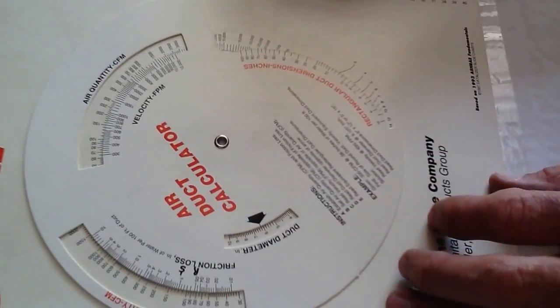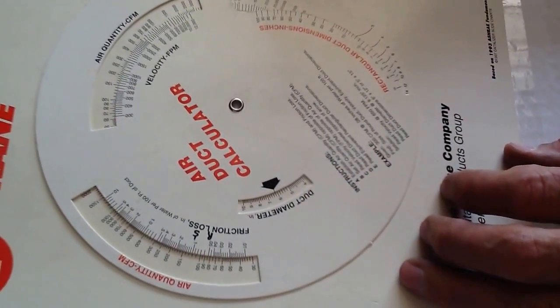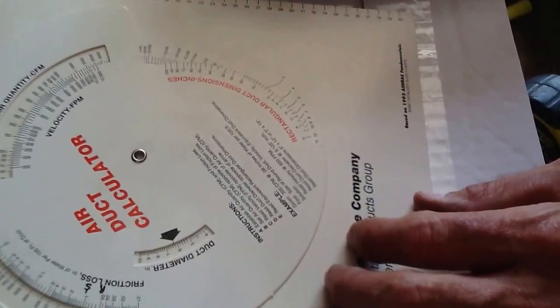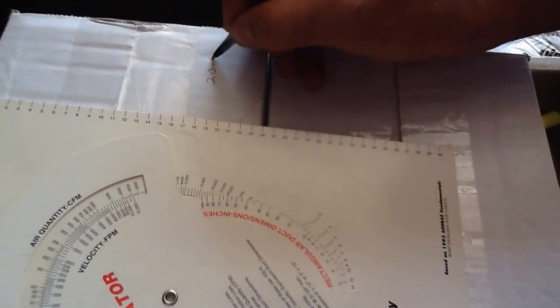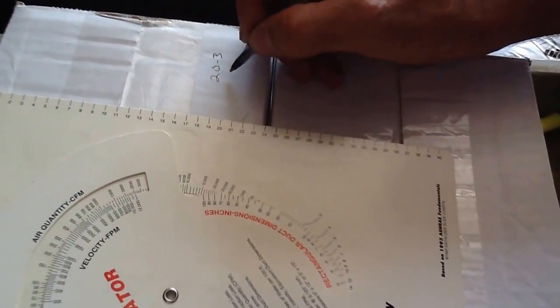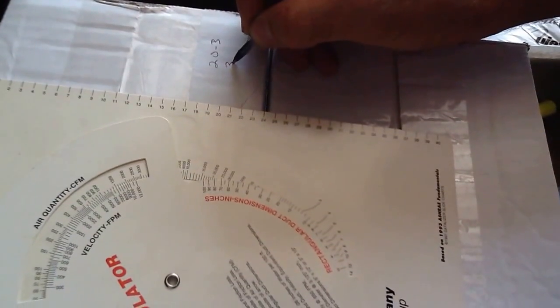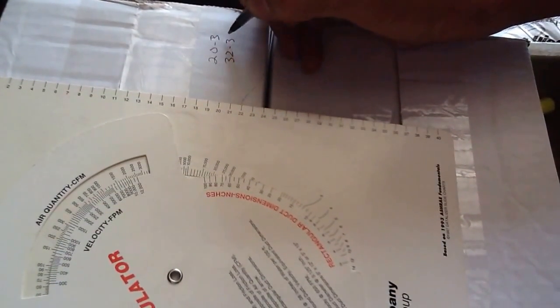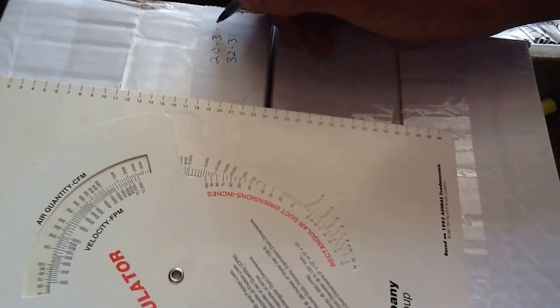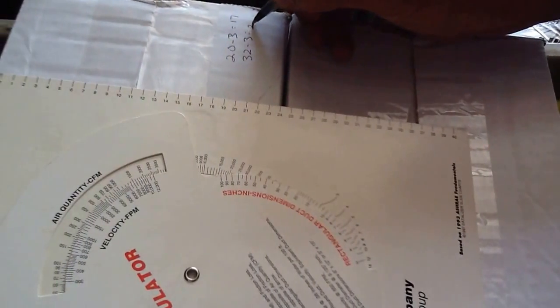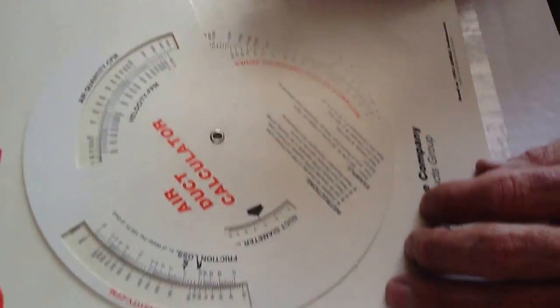We're going to subtract - let me just show you here - it was 20 minus three inches. Then you're going to go 32 minus three inches. So we're actually going to go 17 by 29 rectangular duct.